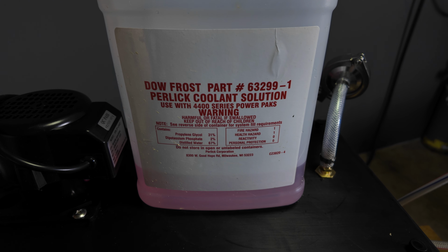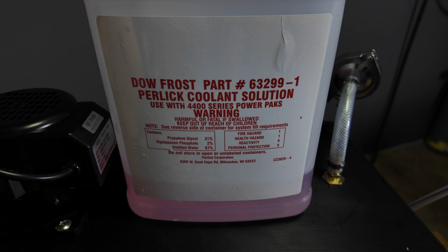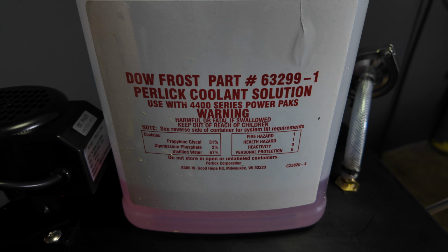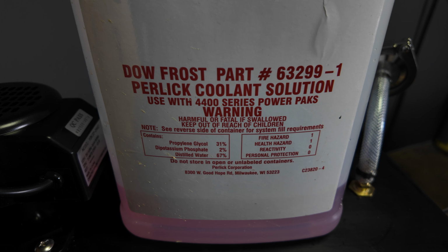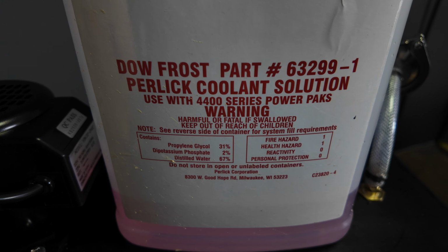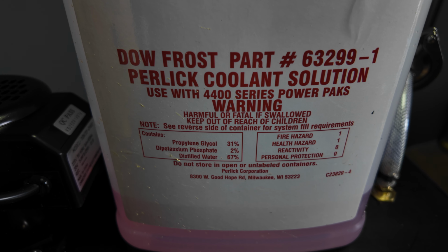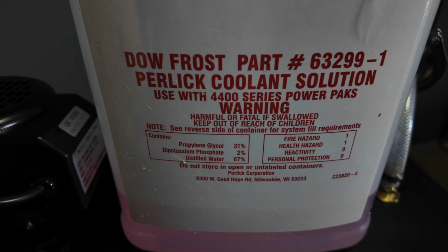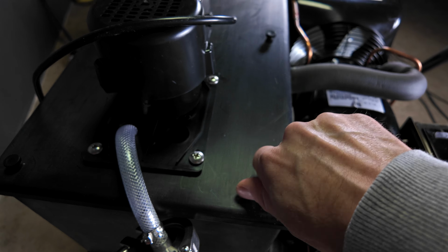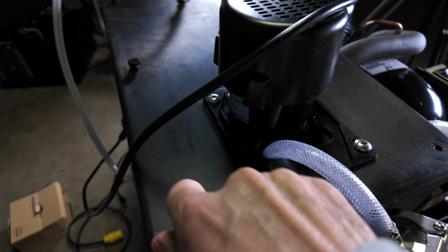For your Glycol, you want to use food-grade inhibited propylene glycol. The key detail here is inhibited. That means it includes corrosion protection additives that protect internal components, especially copper coils and stainless steel, from long-term damage. Do not use automotive antifreeze or ethylene glycol. That's toxic and not suitable for brewing environments.